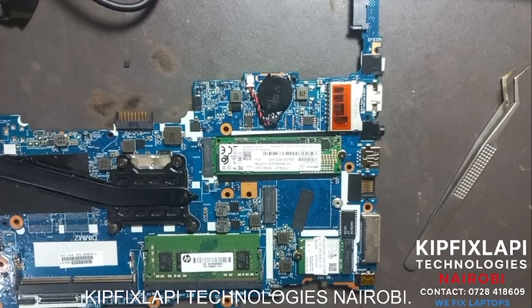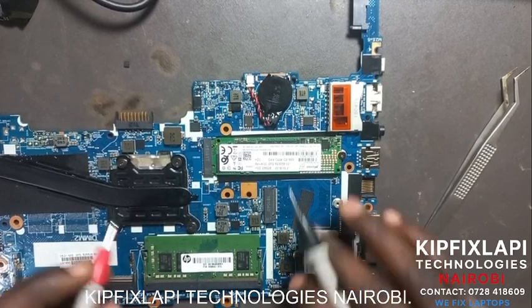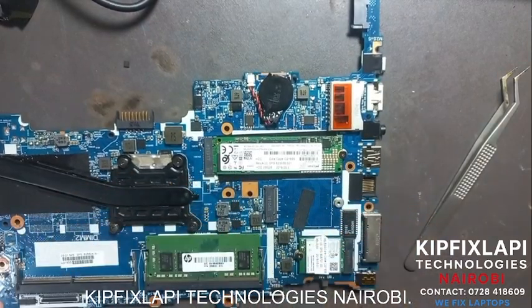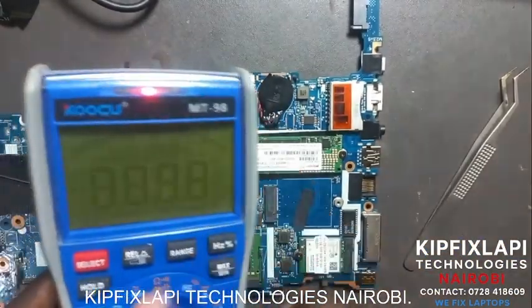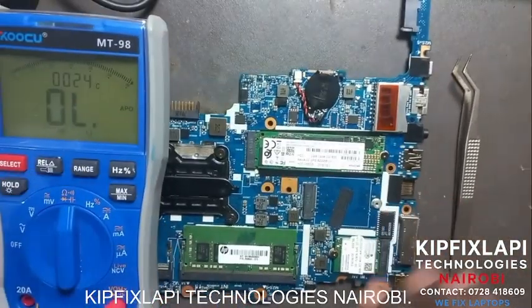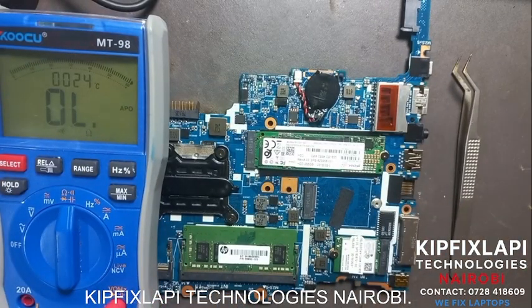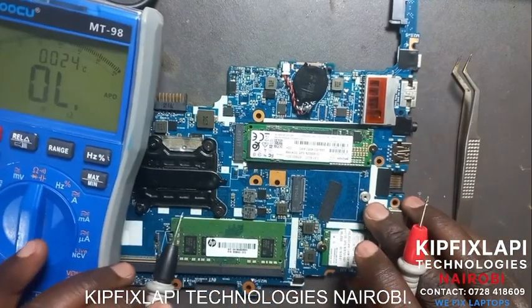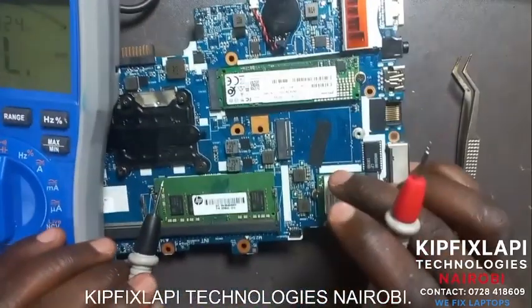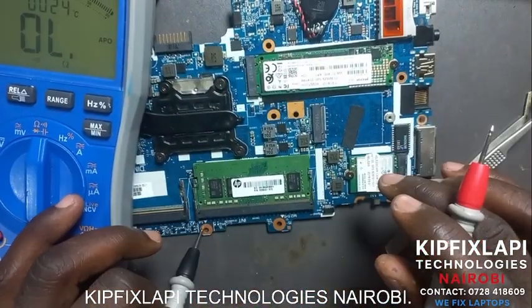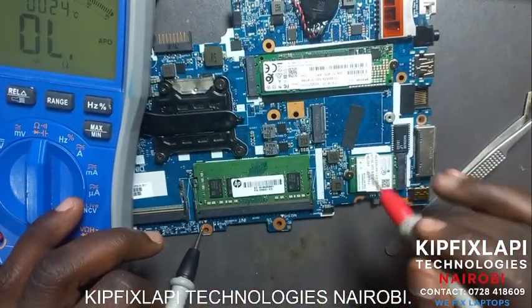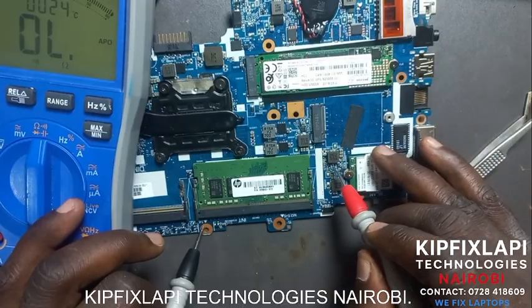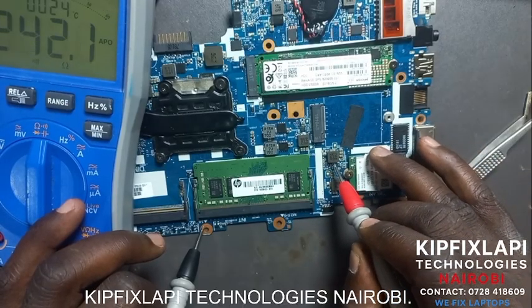I think the best thing to do is to check again whether we still have a short. My meter is off, let's put it on, beeping mode. One probe is always still to the ground, I need one probe to the ground, and then my other probe to this line which was shorted.